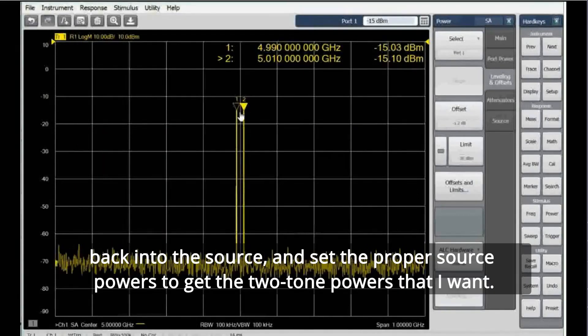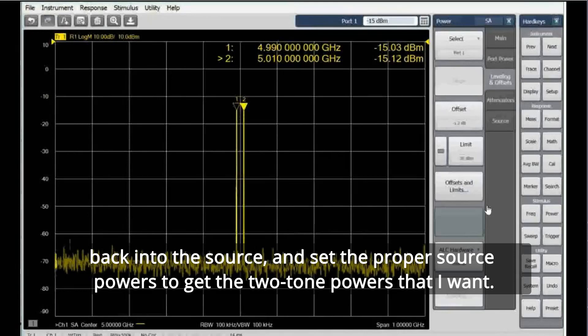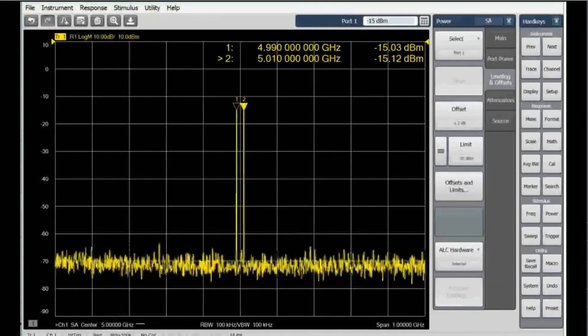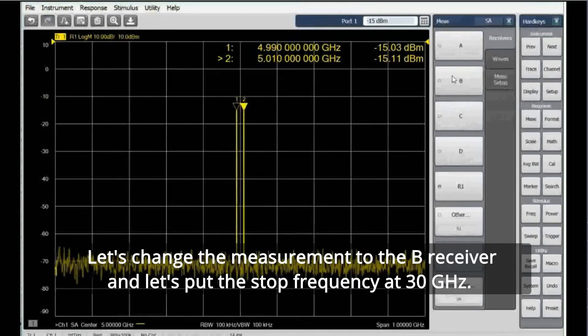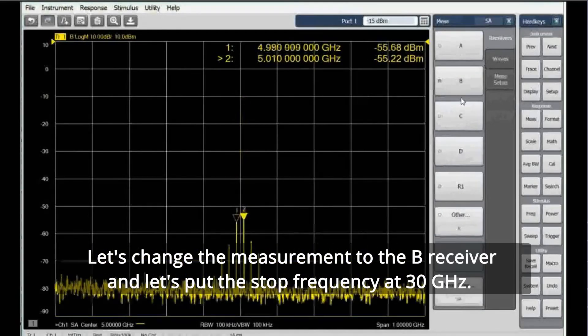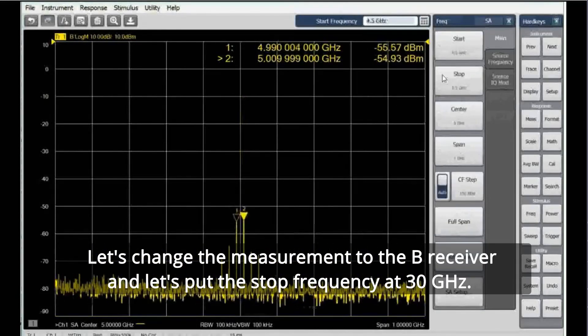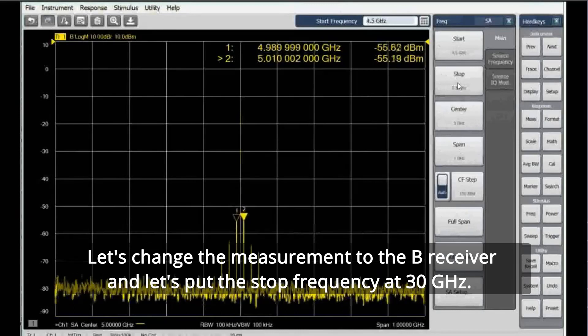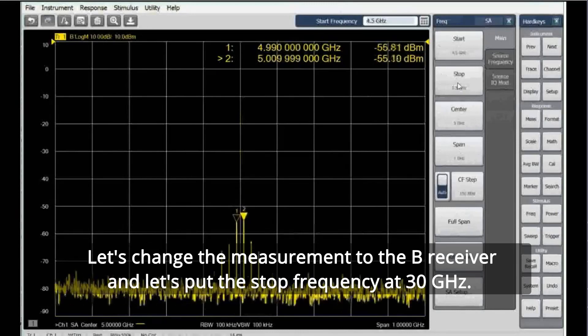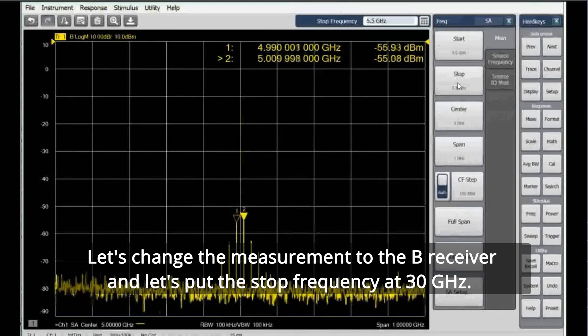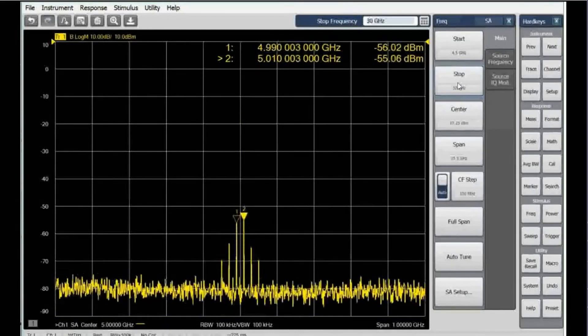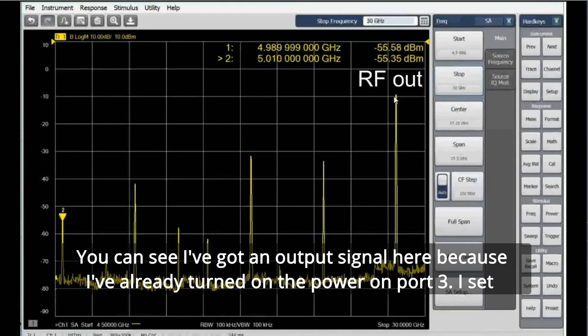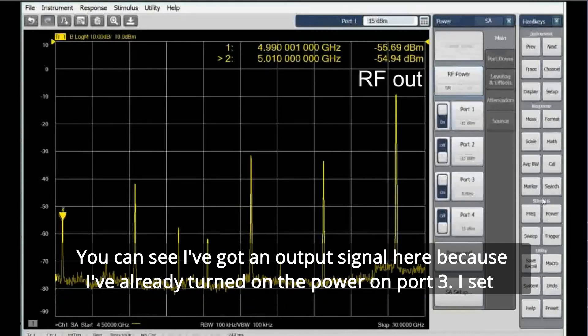We'll go back into the source and set the proper source powers to get the two-tone powers that I want. Let's change the measurement to the B receiver, and let's put the stop frequency at 30 gigahertz.